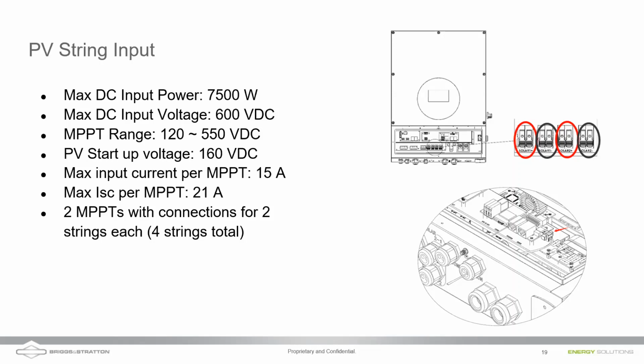If you have more than 4 PV string inputs, you're going to want to either get a PV combiner or look at additional inverter units. So each MPPT splits this power, so you can have 3750 watts per MPPT, max DC input 600 volts. This is the open circuit voltage.